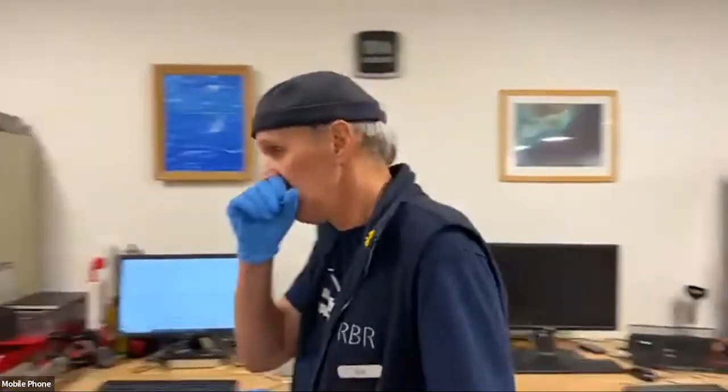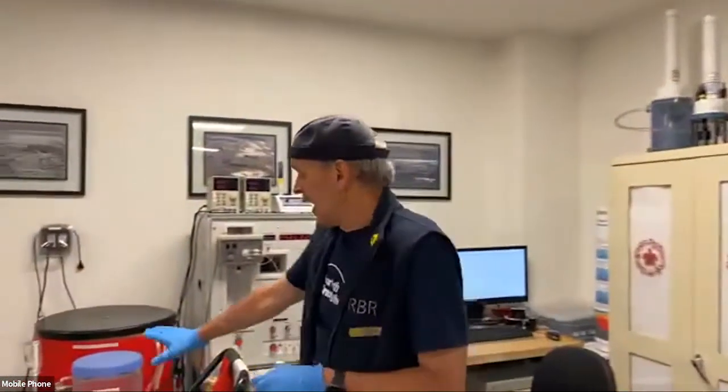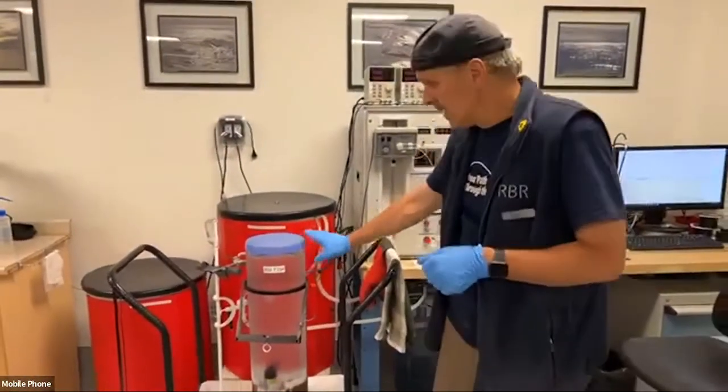But throughout it all, conductivity calibration happens even at the stage of temperature calibration, when we investigate and correct offset and temperature dependence. And even in the pressure sector, when we evaluate performance of the conductivity cell assembly and all variation associated with pressure effect. For example, we just removed what's called a saltwater bladder.